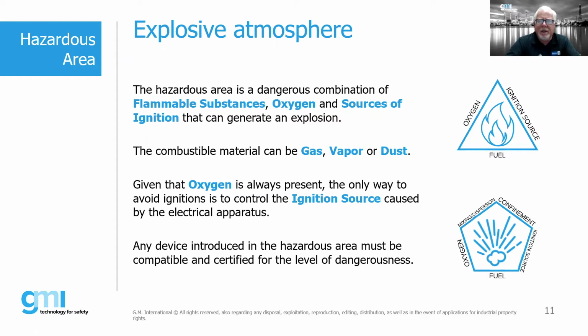The ignition sources that we commonly talk about are referenced in various EN standards as well as IEC standards, as well as NFPA standards. They're things like hot surfaces, arcing and sparking devices, stray currents, exothermic reaction. All of these various things are ignition sources that we have to deal with. And when we're applying electrical and instrumentation equipment into these hazardous areas, we have to take into account all of the potential ignition sources. So we have this combination of oxygen, fuel and some sort of ignition source, and if we get those in the right combination, then we can certainly have an explosion.